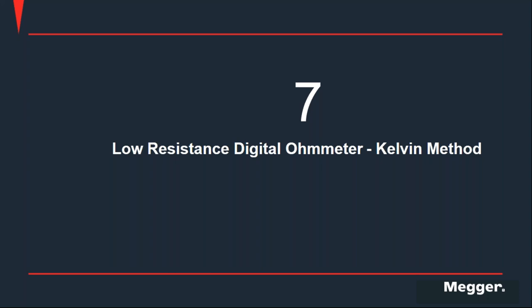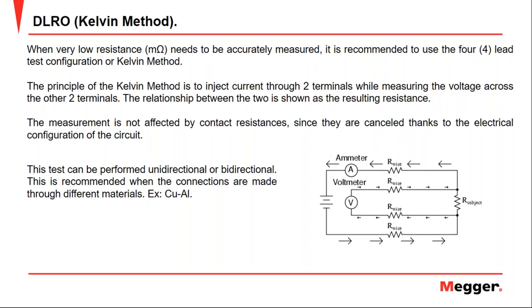Let's talk now about the Kelvin method. When we're talking about very small resistance measurements, we can't use the continuity measurement method. We must use a much more precise method to be able to perform the test. For these cases, the Kelvin method, also called the four-wire method, is used. Through this circuit configuration, the measurement eliminates the error from the cable and the contact resistance, making the measurement much more accurate.